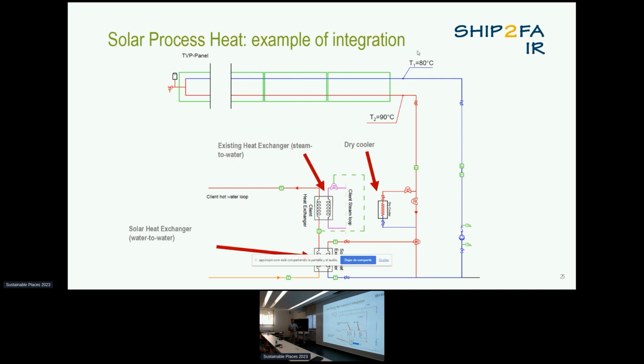In this diagram, you can see the solar panels on top, and the primary circuit with the blue line (return) and red line (hot water) that goes through a heat exchanger to the processes. In case we produce excess heat in the solar system, this dry cooler dissipates the heat to the atmosphere. Where there is not enough solar heat, or no solar heat, the client's circuit operates as it used to before we installed the solar system.